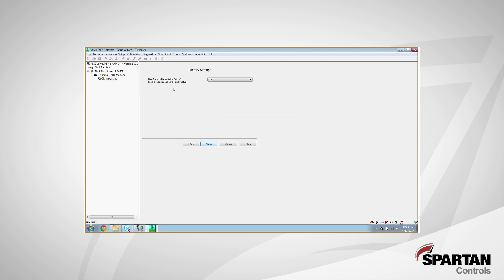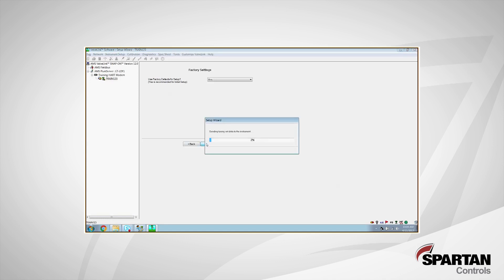And lastly, it's going to ask us if we want to set our DVC back to factory defaults. If this is a new installation, this is great. It's going to erase everything in the DVC and start fresh. But if this is a DVC that's existing and you have custom settings in there, whether that be custom characterization, custom cutoffs or alerting, you're going to erase all those settings and go back to factory defaults. So just use this on their first installation and after the fact, think about whether or not you want to be setting back to your factory defaults or not. I'm going to click finish. It's going to send all this information to our DVC and in our case, set it back to our factory defaults as well as put our actuator information in there, our tuning information.